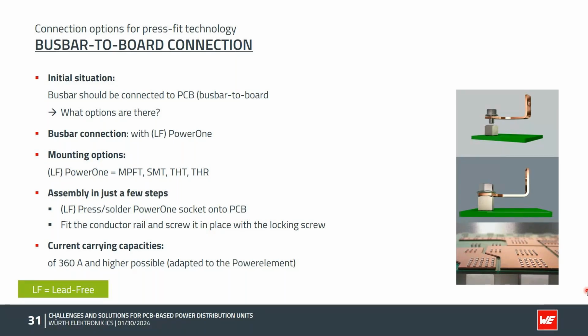In addition, or as an alternative, it is also possible to press the busbars directly into the power element, as shown in the picture below. This is often used when higher currents need to be distributed locally, but you don't want to use a thicker PCB.